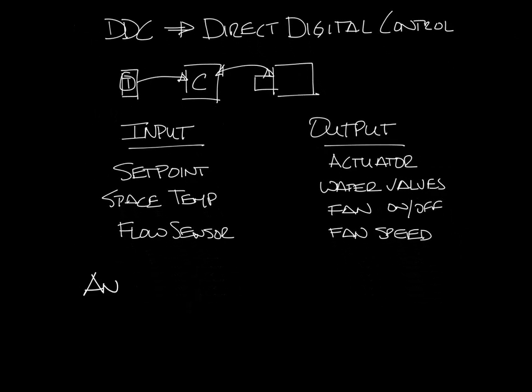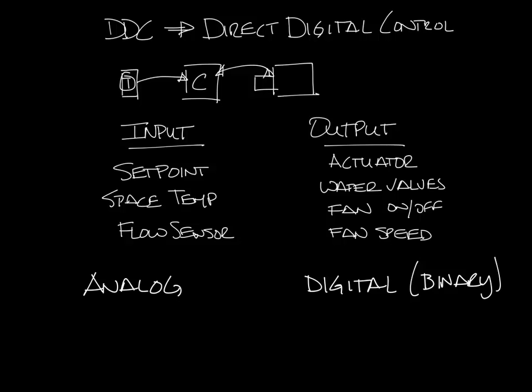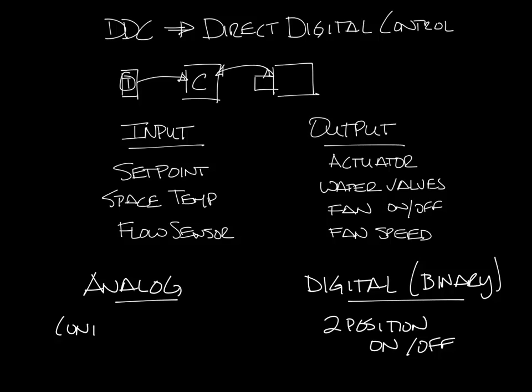DDC controls have two types of inputs and outputs: analog and digital, which is also known as binary. Digital inputs and outputs are two-position, usually on-off, whereas analog inputs and outputs can be anywhere within a continuous range. Think about how an analog clock hand sweeps between the minutes, but a digital clock is always on a particular minute.